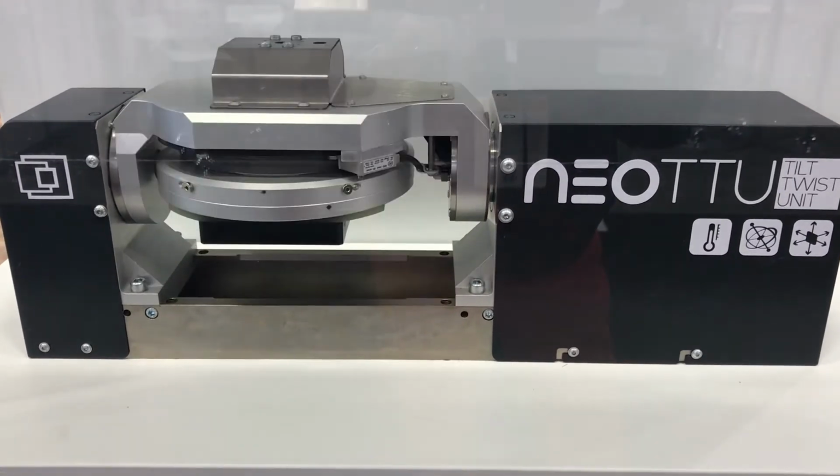In this machine, you can see we have a couple of pressure chambers for pressure sensors, but in the case of an accelerometer or a gyroscope, another device that we have in our cell phones, for example, you need to physically stimulate the device, giving acceleration and angular speed. So this is to mimic real-life use while you're testing it.